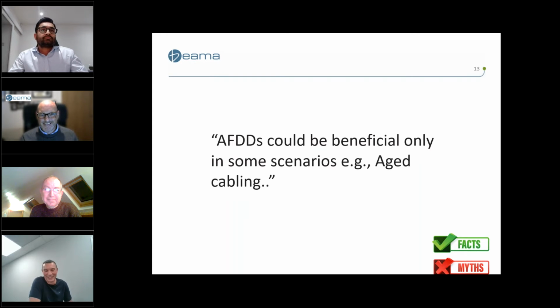Ian? Okay. All right, so AFDDs do provide protection for aged cabling, but they also provide a lot of additional protection. So we're talking about things like rodent damage, pierced insulation, kinks or breaks in flexible appliance leads, incorrect wire stripping, cracked or crushed cables, deteriorating insulation. There are a number of different elements here that cause arcing faults over a period of time. So it may not be something that generates instantaneously, but it may develop over a period of months or even years.